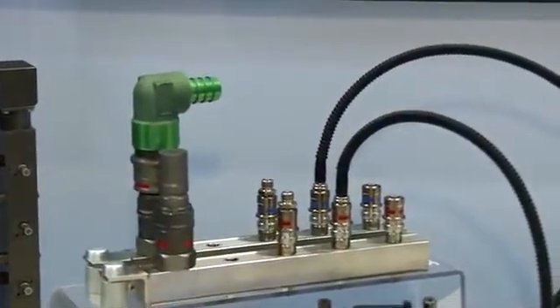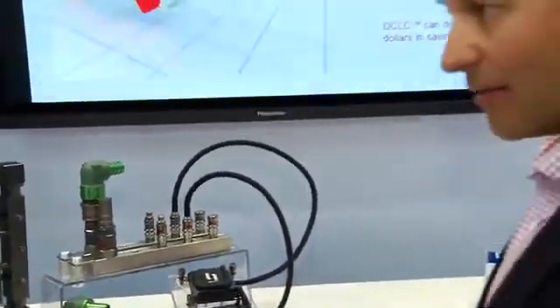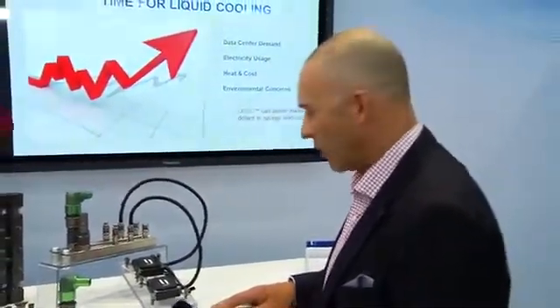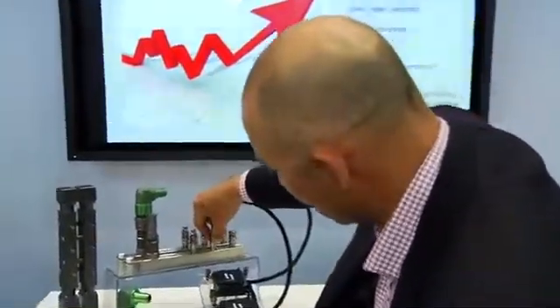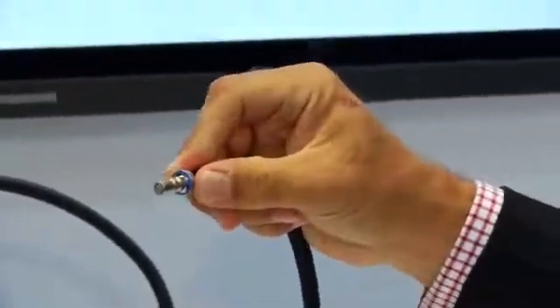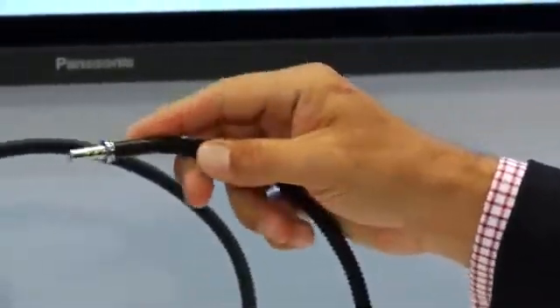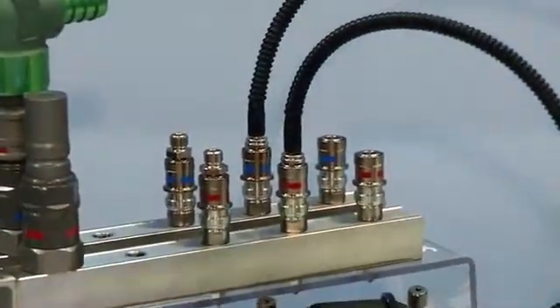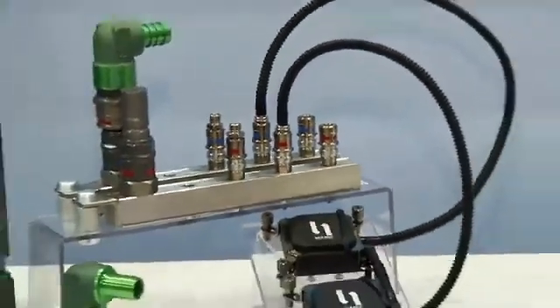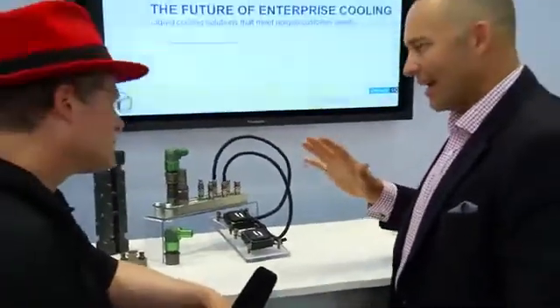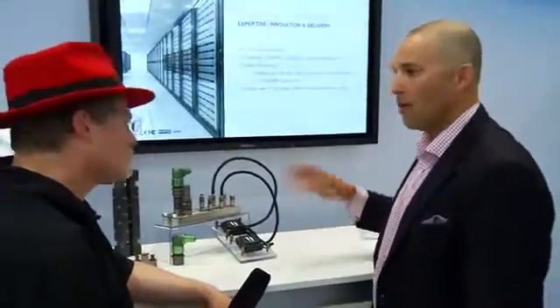So what are we looking at here, Jeff? We've recently announced a partnership with Stäubli, the world authority in dry break quick connects. Notice they're all metal construction. We have these connections on our manifold, and they guarantee it's not just drip-free, but actually dry when it breaks. The philosophy is that no special skills should be required to hook this up or disconnect it for serviceability. Beyond that, when a data center invests in this manifold system, it's going to be there for years to come - the manifold will probably last much longer than the server, and nobody wants to take chances with liquid getting out.